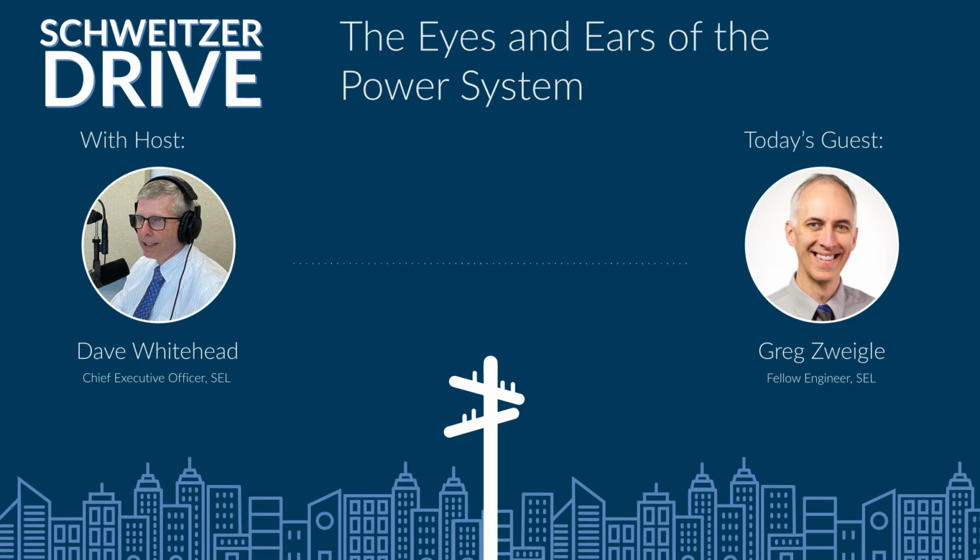Yeah, exactly. So with SCADA, because the measurements were taken relatively slowly, we really couldn't get a precise measurement of the state. And as engineers, when we say state, we mean all of the measurements needed for a system in order to be able to predict what it's going to do next. With synchrophasors, with these high-speed measurements, we now can directly measure the state instead of having to estimate it. And that's been a really important improvement.